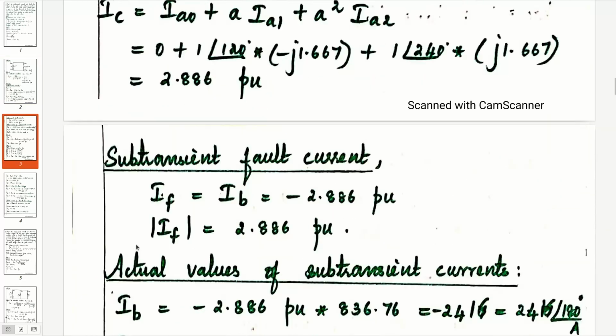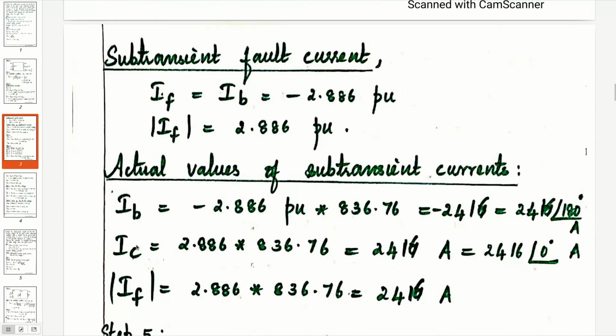After finding the generator terminal currents, we have to calculate the fault current during the subtransient condition. It can be denoted either as IF double dash or IF. From the derivation, IF is equal to IB, and IB we got as minus 2.886 per unit from the previous calculation. Taking only the magnitude, it is 2.886 per unit. These values of the subtransient current are in per unit, so multiply by the base current to get the actual values.